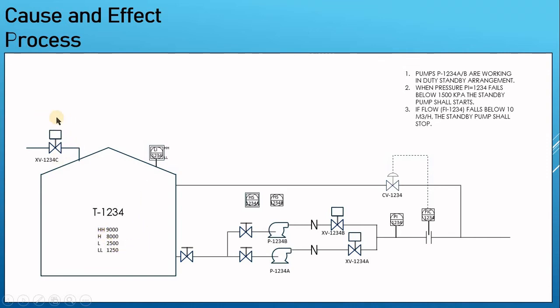For the high-high, if the level goes to high-high, you may need to close the inlet valve — and since this valve comes from a pump, you may need to trip the upstream pump as well. In this P&ID you also have DCS represented by one square, and SIS represented by two squares. So this is an SIS transmitter and these are SIS push buttons. The high and low levels are alarms; the transmitter has high-high and low-low, so we are missing another transmitter for process control to give the two alarms — although you can also generate alarms from the SIS or trip transmitter.